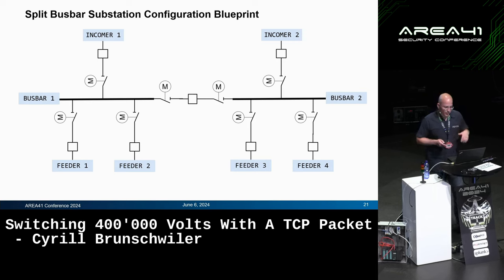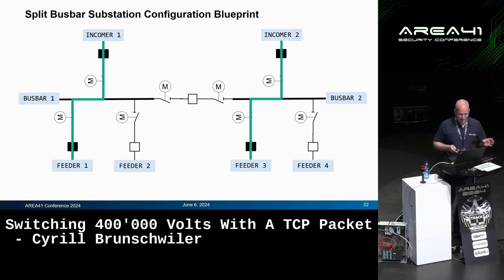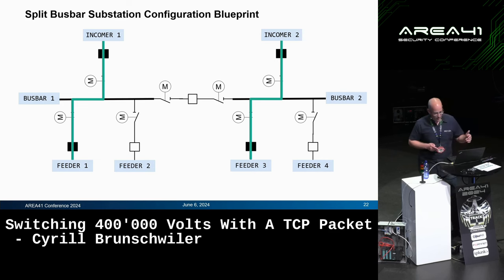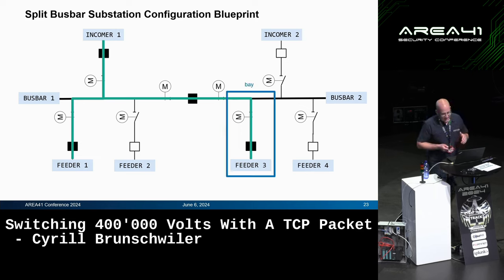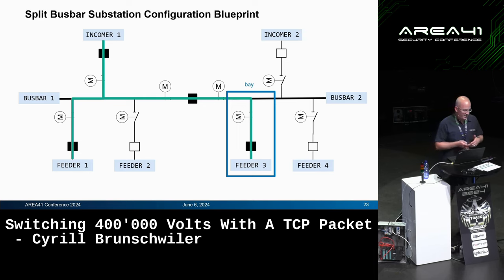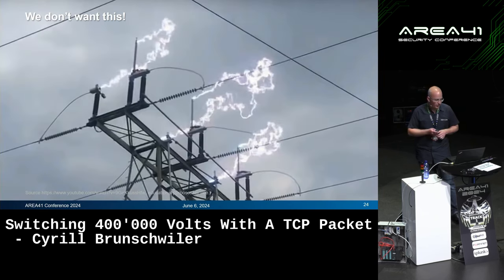When designing a substation, we have incomers, feeders, and bus bars, designed for redundancy — there are many different configurations. Current flows from incomer one to feeder one; if you want to do maintenance on incomer two, you close the center breaker and free up incomer two. Part of this we call a bay. The process within the substation is to keep the bay safe and check if surrounding bays might interfere. We need to be very careful about switching order to avoid shorts and faults — for example, never open a switch before the breaker is open.